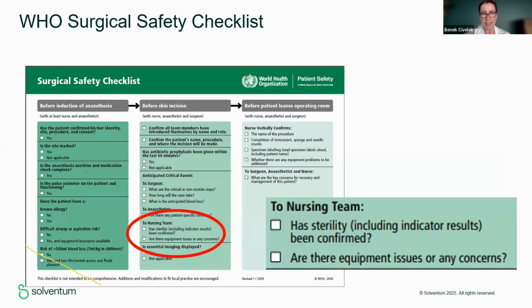Internal pack monitoring. The best practice again is putting one internal pack indicator in each pack to see if, for instance, for steam, time, temperature, and the most important part, saturated steam, is inside every pack. And this is an example wherein the WHO surgical safety checklist is also telling the nursing team to check the internal pack indicators. So, has sterility been confirmed?